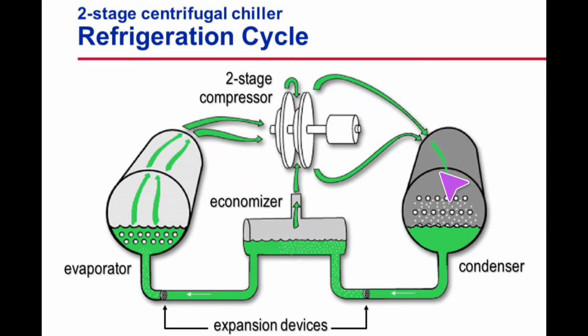We come into the condenser. So the condenser is just a standard everyday condenser, right? There's nothing really fancy going on here on a Trane machine. We're just processing water through pipes. It pulls the heat out of the refrigerant and then sends it off to a cooling tower. Anyway, coming out the bottom of the condenser here, this is where Trane gets a little more interesting. Coming out the bottom of the condenser, we have our liquid line, and you're going to go through a first stage flash, okay? So this is just a flash plate coming into what is known as the economizer.